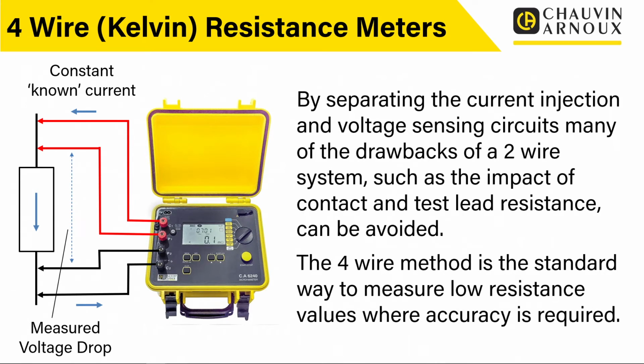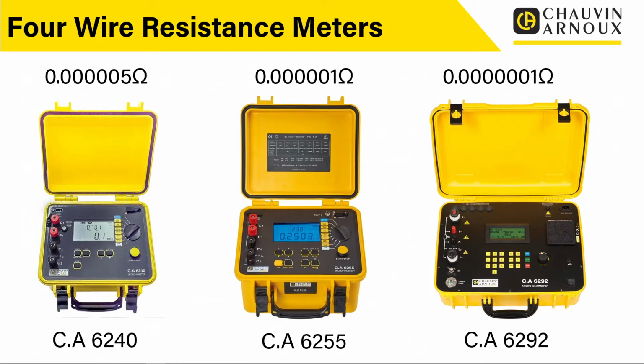So you can see, again, by separating the current injection and the voltage sensing circuits, many of the drawbacks of a 2-wire system, such as the impact of contact resistance and test lead resistance, can be avoided. And this is why the 4-wire method is the standard way to measure low resistance values where accuracy is required. So we looked, a couple of slides ago, at the levels of measurements that you could get out of the standard 2-wire type tests. We were talking about maybe getting down to 0.1 of an ohm, or maybe 0.01 of an ohm. That was the level you'll get to with a 2-wire test.